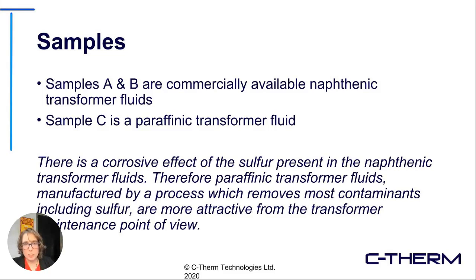In this case, we look at two or three different samples of transformer fluids. Samples A and B are commercially available naphthenic transformer fluids. Sample C is a paraffinic transformer fluid. Generally speaking, paraffinic transformer fluids are more commercially attractive because they're not as prone to contamination with sulfur-containing compounds, and therefore they don't tend to have as corrosive an effect on the transformer electronics.